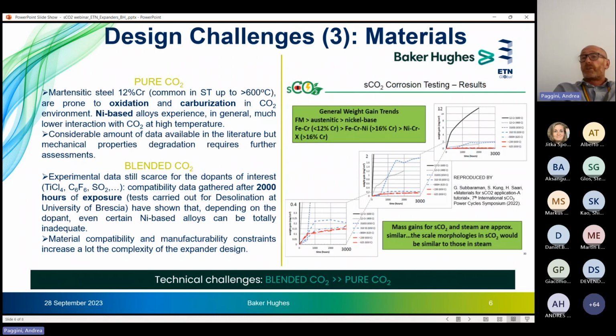So what are the design alternatives at disposal when designing these machines? Number one is to switch to other materials. I picked here just one graph from the enormous amount of literature available, where you see that austenitic steel behaves better in terms of material compatibility with CO2. Nickel-based alloy is even better. Option two might be to maintain martensitic steel for certain components, providing a protection layer by means of coatings or cladding. Option three might be a dedicated cooling of some specific components, or even all the three options combined together.